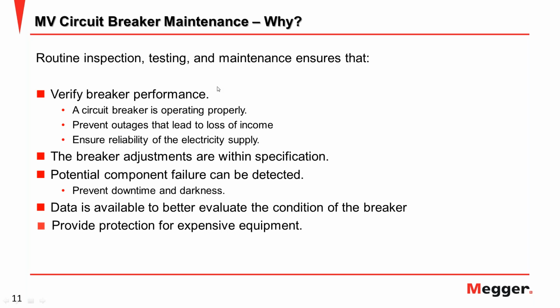The main purpose why we need to test is to verify the breaker performance, to check the circuit breaker is operating properly, and to prevent outages that lead to lost income. So this is the end goal. We don't want the loss of income because our system shut down caused by breaker failure. And also we need to verify the breaker adjustment is within specification. After you buy a breaker, mostly you need to test to make sure the breaker specification meets your requirement. And data is available to better evaluate the condition of the breaker. So if you test the breaker at the beginning, at least you have the data that can be used to analyze if you have a problem in the future.